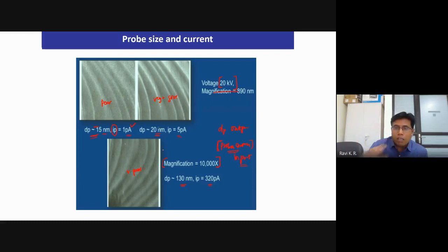What we do is keep a particular constant aperture and the particular microscope. By varying the probe current, you can optimize the image also. This parameter we don't usually touch, but this is another thing that we need to see. Basically, the probe current gives you a signal to noise ratio. But again, that number doesn't make any sense by itself.